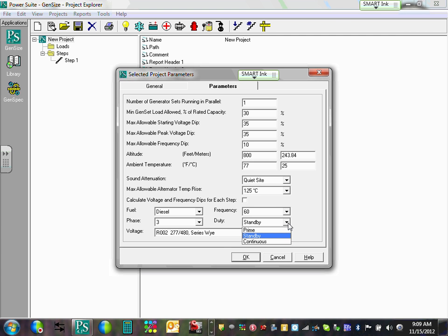Do you want the generator to, like data centers? Yes, but the building is not running and you lose power. You can program it not to run for a certain amount of time. It's all in the programming. Yeah, no, you don't want it. If you lost power and nobody's there, do you want your generator to come online? No. All part of your governor of the generator programming.